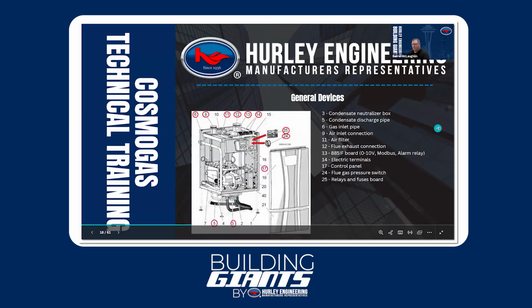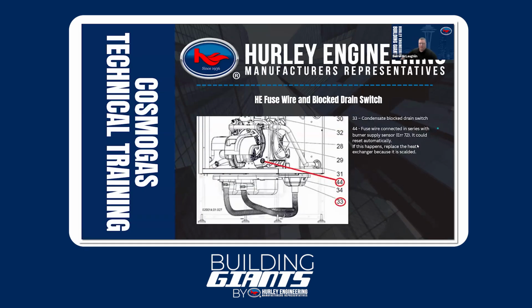And here we go. So this is the drain switch. If we start to have our condensate drain back up, it needs to be cleaned, or for whatever reason, this switch would stop it from backing up into the heat exchanger and causing excessive corrosion or problems with the burner ignition. So that's where that's located right there. And then we've also got a fuse to protect the heat exchanger from failing catastrophically. So we'll cover that here just a little bit as well.